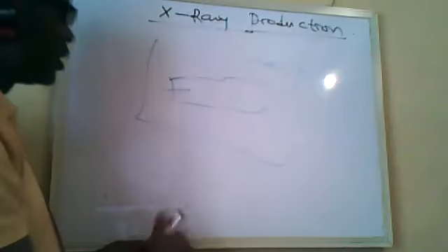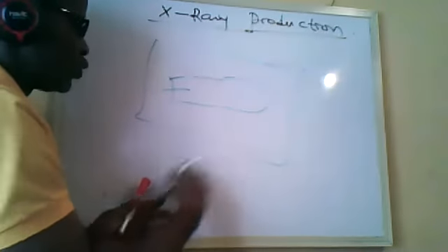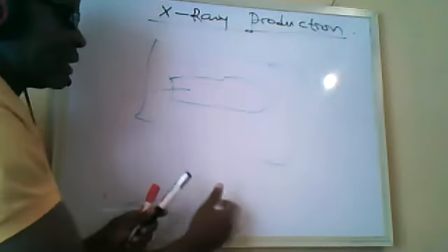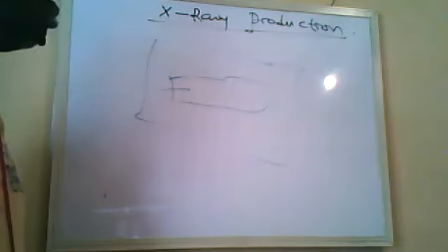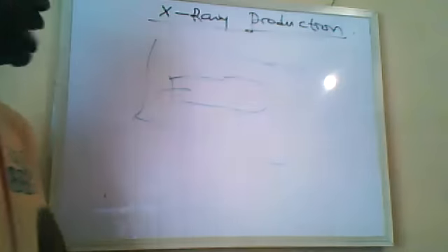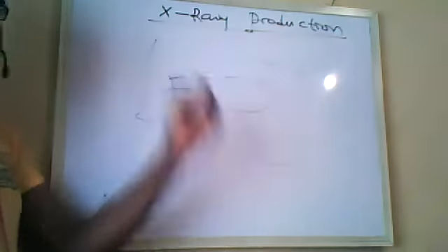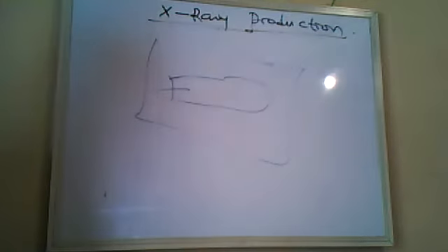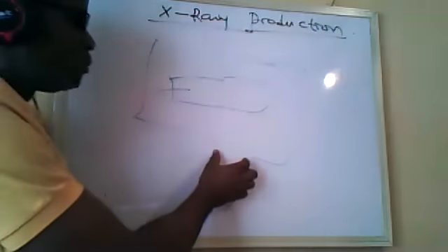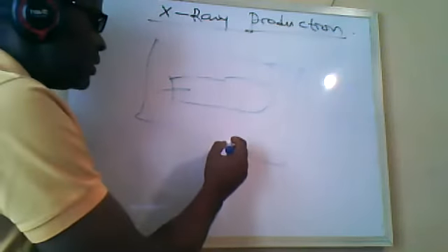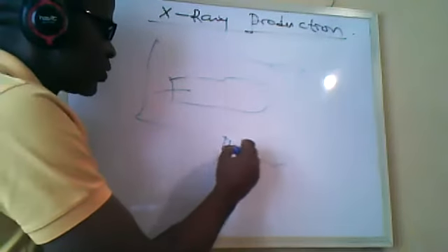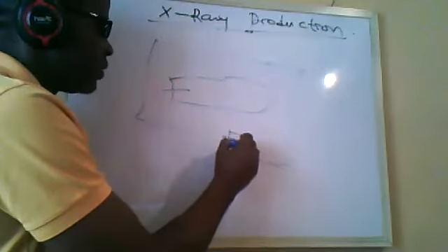So it is not just the window where you want to get the X-rays from. X-rays are produced every other place, so you have the leaded walls everywhere. All the components of the X-ray tube are leaded. We just leave a small portion which contains our collimators that define the X-ray field.